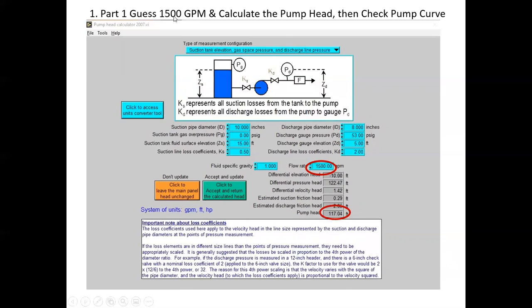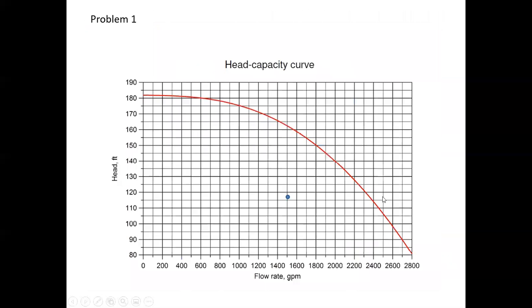So I just said, what the heck, I'm going to throw 1,500 in here. And then the calculator calculates the pump head at just a little over 117. Okay, so remember that: 1,500 GPM, 117 feet. Then we go to the pump curve, the head capacity curve.